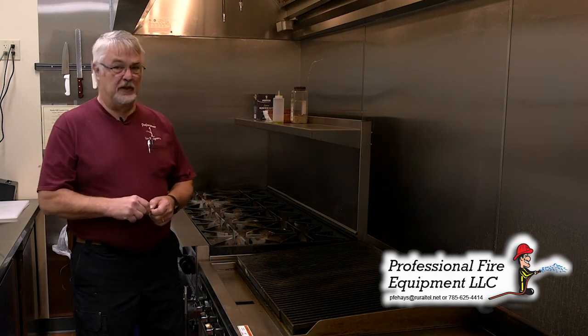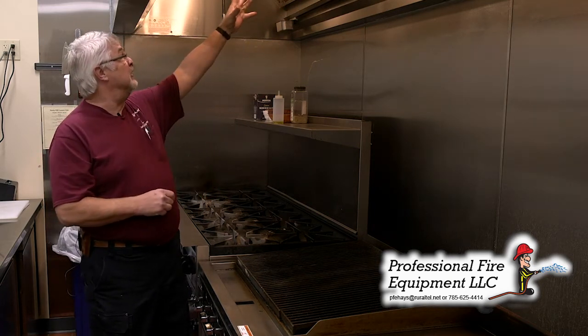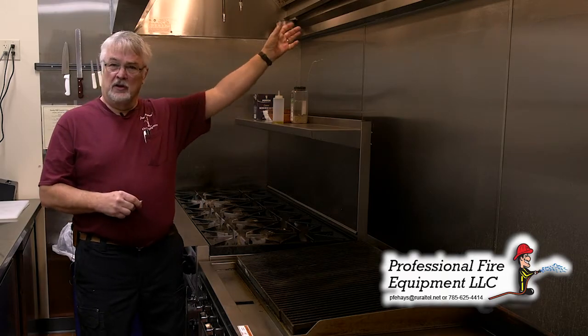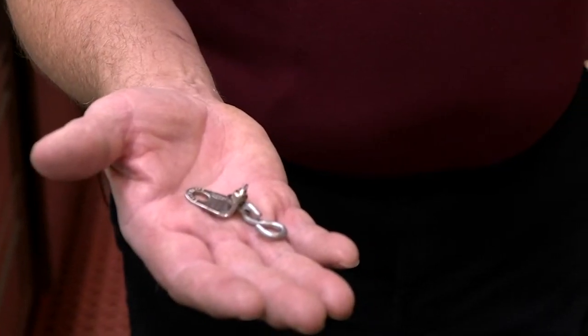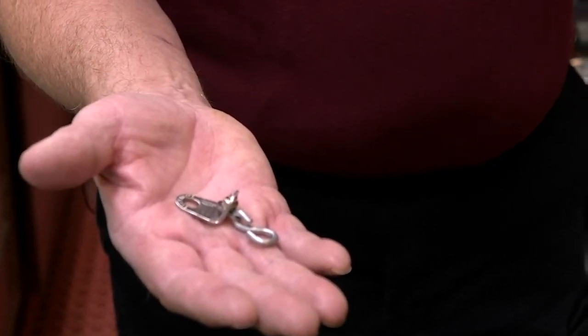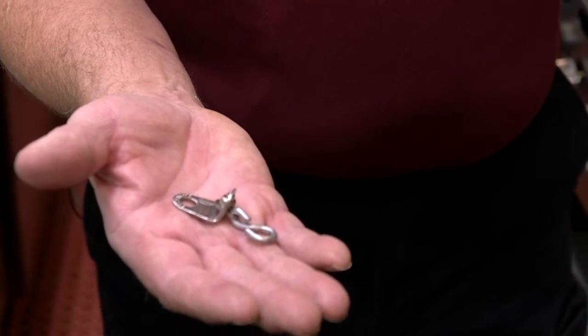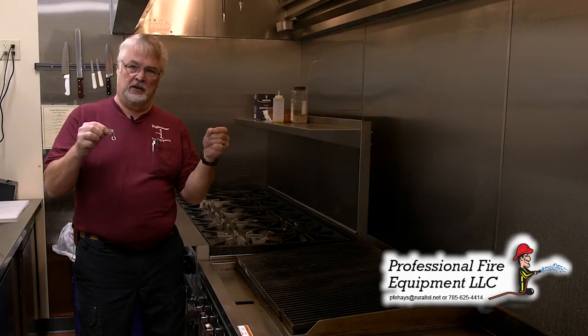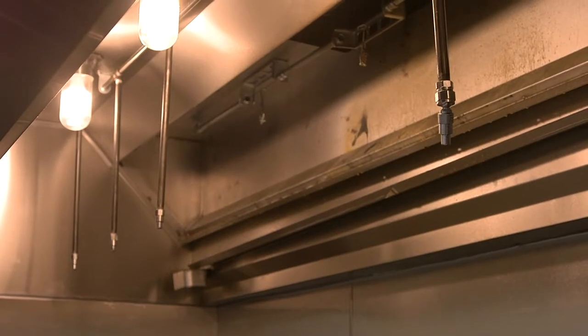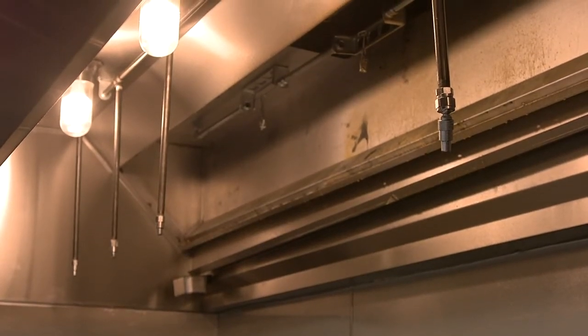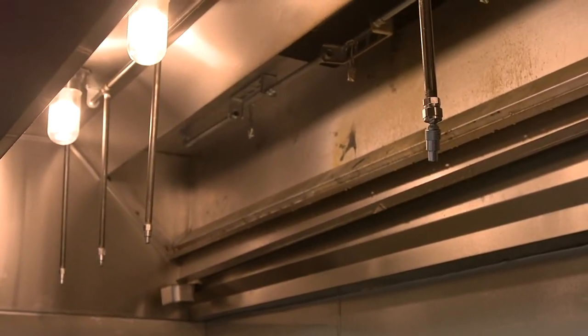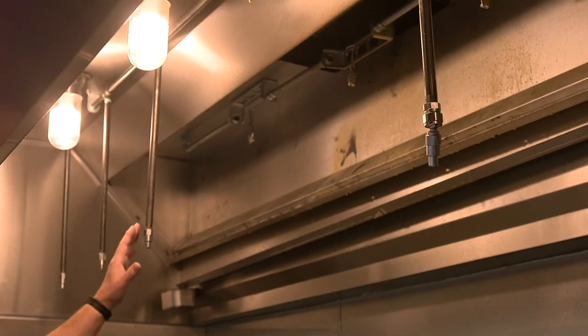What will happen is, in the event of a fire, you have fusible links up inside your exhaust hood. What they are is two pieces of metal that are soldered together. They'll melt and break, and that's what sets your system off automatically. You'll have chemical coming out of each one of the nozzles, behind the filters, and up in the ductwork, all at the same time, and the system will dump completely.